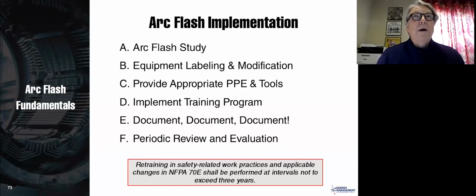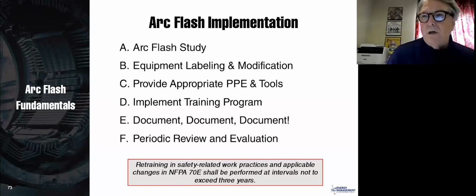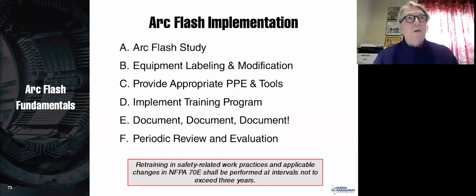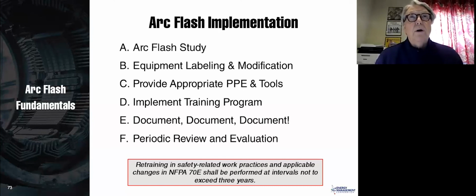Now, if there is somebody in there, they're taking voltage measurements, they're putting CTs around to measure current, they're moving a wire so that they can read that, all of that would be considered work. And if there's any kind of work that's going on, then you cannot be within the arc flash boundary without your burn gear on. And so I would generally say, for the most part, the definition of work means that somebody is in the restricted space. And if there's somebody in that restricted space that is within 1 foot of the gear, then I say no matter what's happening, work is going on.